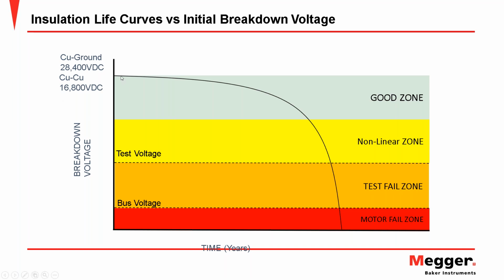And again, the reason they're designed this way, with this highest voltage at the beginning of life, is so we have room to degrade over time. If I want a motor to last 10, 15, 20 years, I'm going to have this high insulation capability at the beginning of life so that it has room to degrade over time. Of course, we showed this graphic in the static testing, where by periodically testing to evaluate that we're in the good zone, we start to see some departure from linearity, or maybe even surge pulse to pulse EAR indications, and then that would give us some predictive indication that we're arriving at the motor failure zone soon, reaching the end of life, if you will, so that we can start to take proactive measures to plan a change out or clean and inspect or whatever is required to maybe move us back up into the green zone. Of course, once the tests start to fail, then we're near the end, and we just definitely have to plan on changing out the motor.